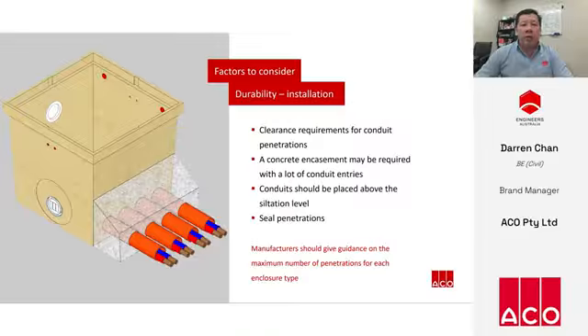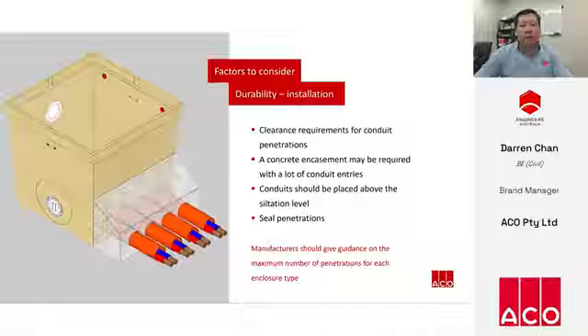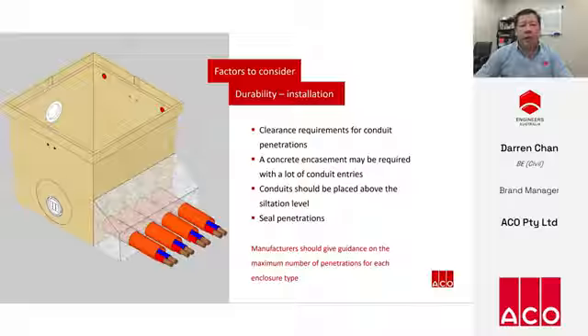The arrangement of conduits within the cable route will determine how many penetrations are required on the walls of the enclosure. Factors that can determine the maximum quantity of conduit penetrations a pit will accommodate depend on the pit material type, pit size, and frequency of traffic. A build-up of silt is common in cable pits and can make cables difficult to access, so penetrations should be sealed and conduits should be placed above the base of the pit to avoid damage to the cables. For each enclosure type, manufacturers should give guidance on the maximum number of conduit penetrations and spacing between each.